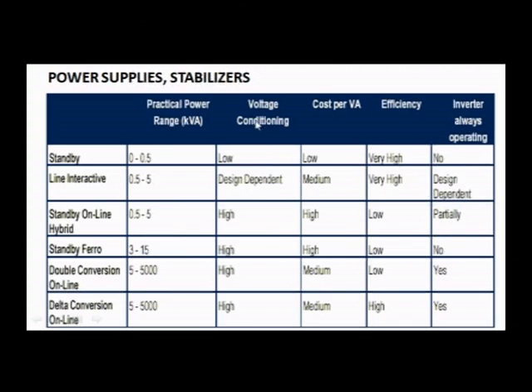Conditioning of the voltage means whether the voltage is conditioned - not only regulation, maintaining the value, but also whether all the other unwanted noise voltages and transient surges are handled. Standby has almost no voltage conditioning; we do not have circuitry for it. Line interactive is design dependent, whereas the other four types have high voltage conditioning, with circuitry involvement for conditioning.